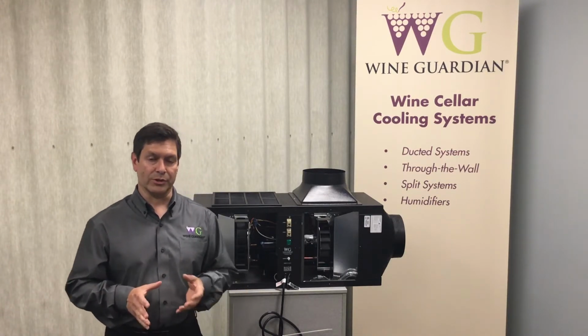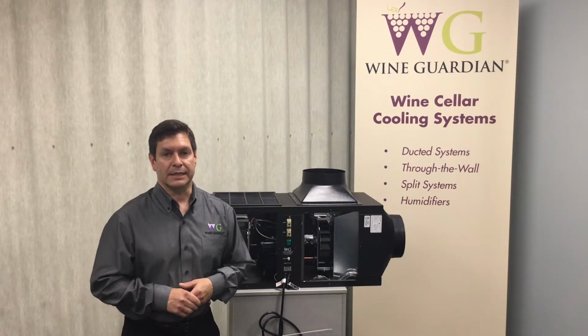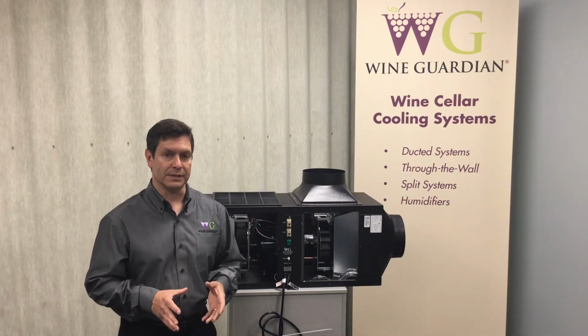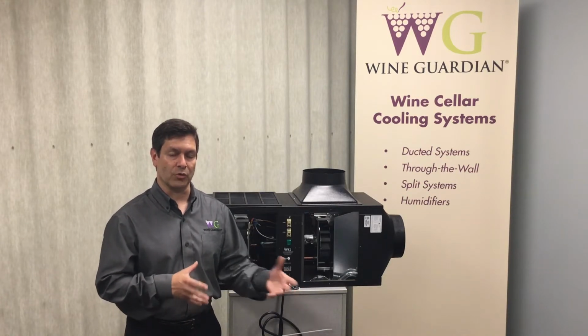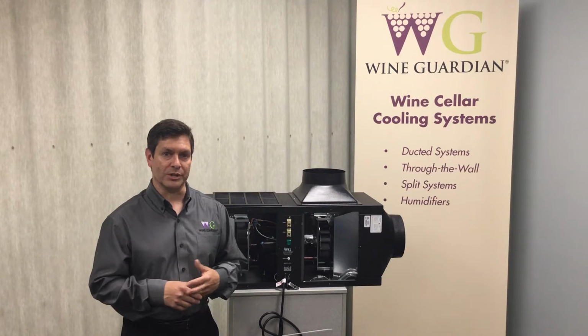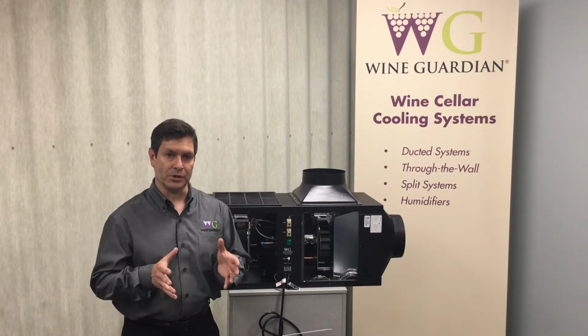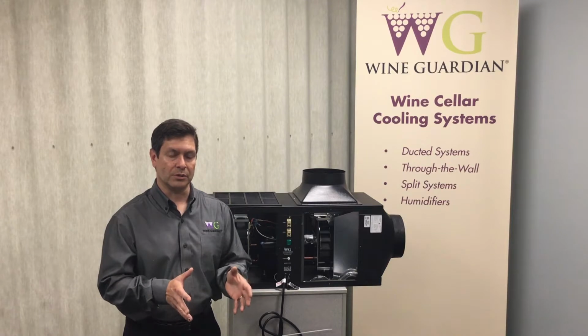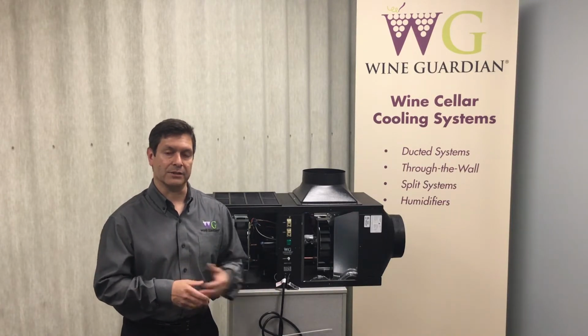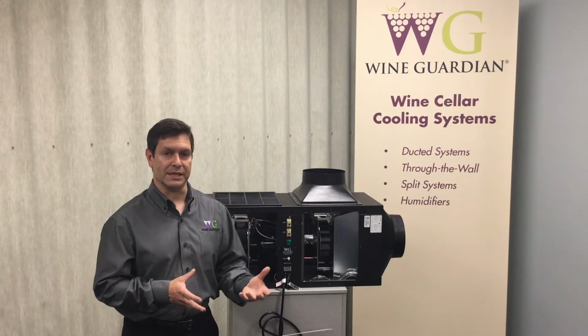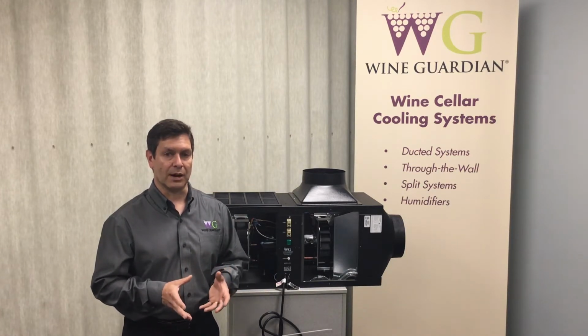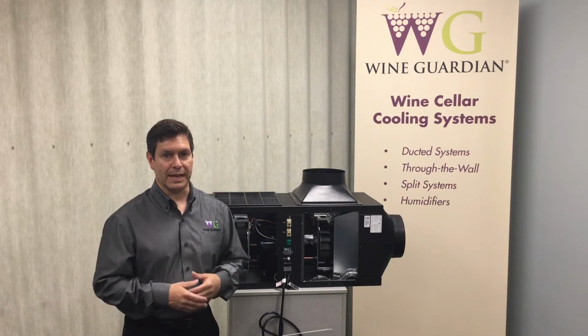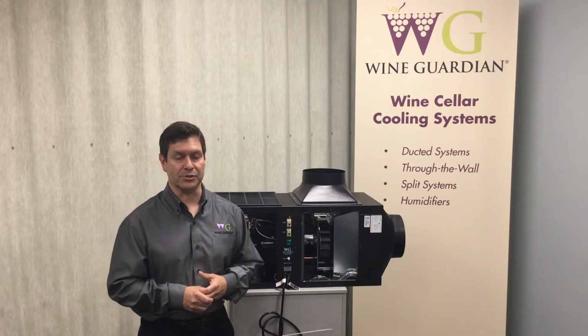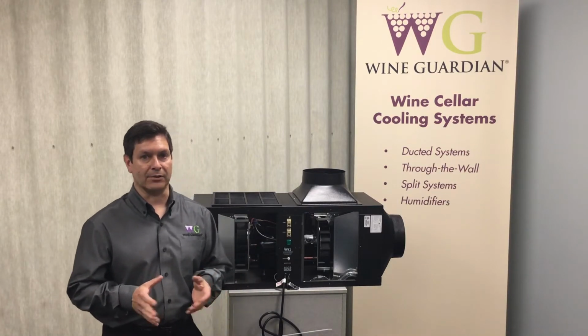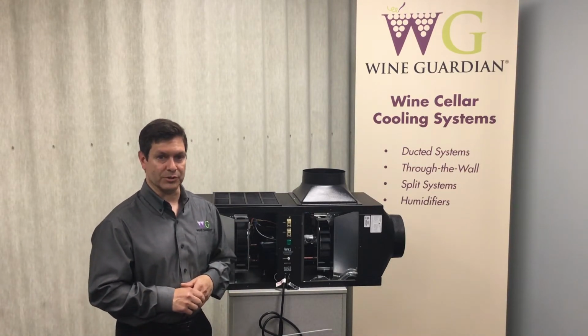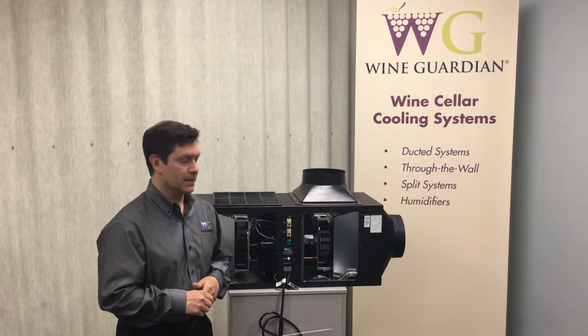What you need to be concerned with when you're applying this option is to make sure that you have enough capacity with the system to get as cold as 42 to 45 degrees for the space. So when you're running your heat load calculation, you want to put in the actual temperature that you want to control, let's call it 42 degrees, in your heat load calculator to see what type or what size system is required. Your BTUs per hour, your capacity, is going to change. It's going to increase as you do that. So be concerned about that and really pay attention to that detail. If you want to maintain those colder temperatures, you really have to understand the BTU per hour requirements.